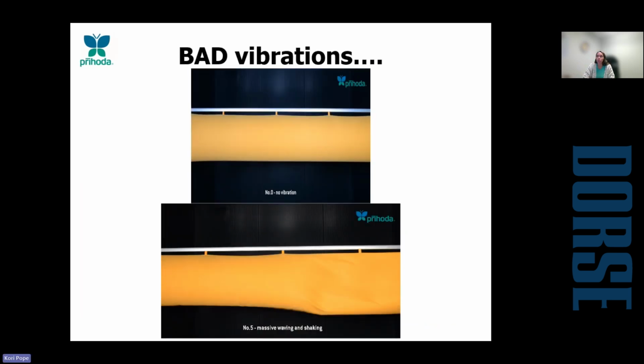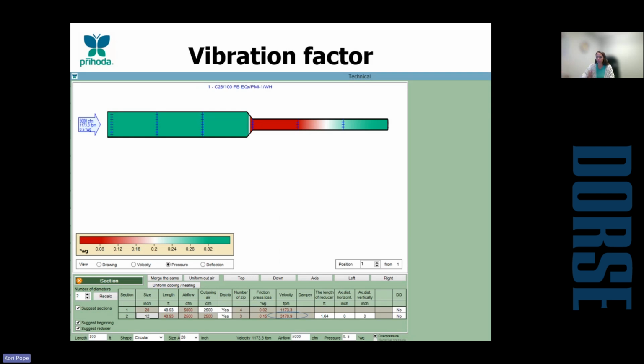So one potential issue with fabric duct is system vibration. The end goal is always to have a completely solid design where your fabric duct is not moving at all. And one way that we do that is with Airtailor. So as we're putting in your full system, it's breaking it out into sections if we were to reduce it.